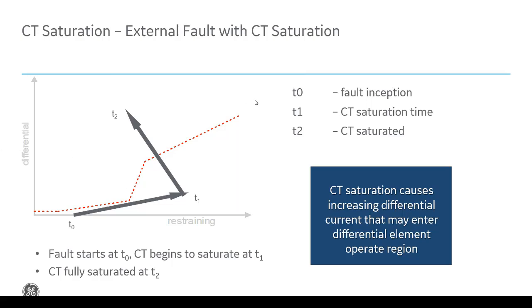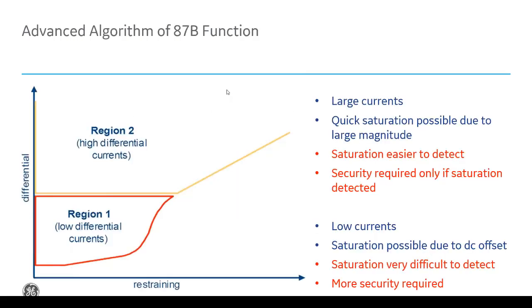However, there's only so much limit to these curves that you can do. So sometimes, if you have some extreme cases of CT saturation, we have another technique within all our relays, what we call a directional principle. Basically, what we'd say is we have a high differential and a low differential. We split the curve into two. And we say, hey, in region number 2, we have large currents, so CT saturation is easy to detect.